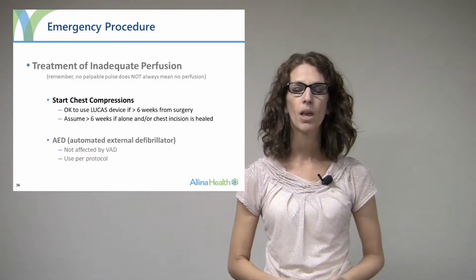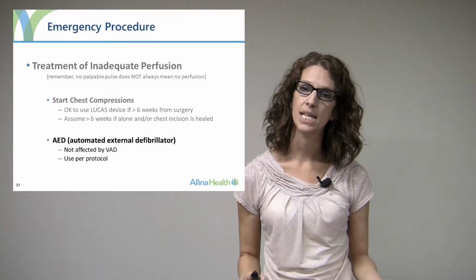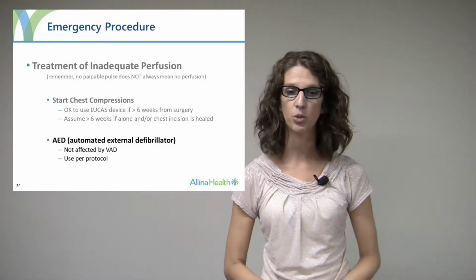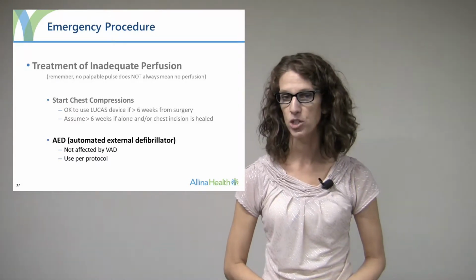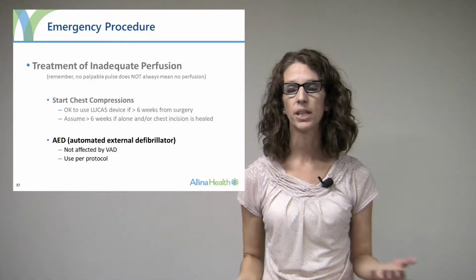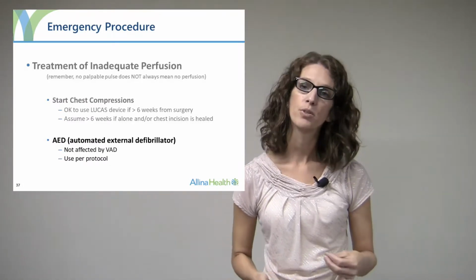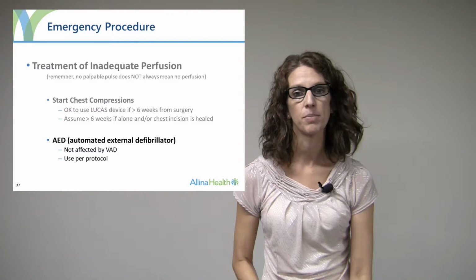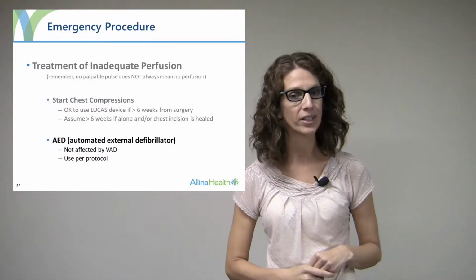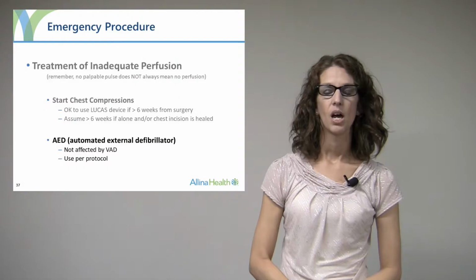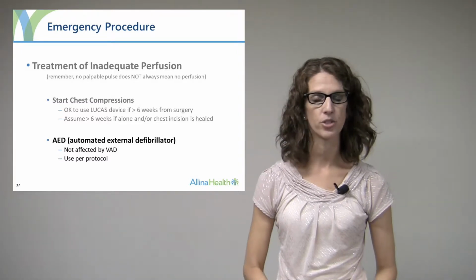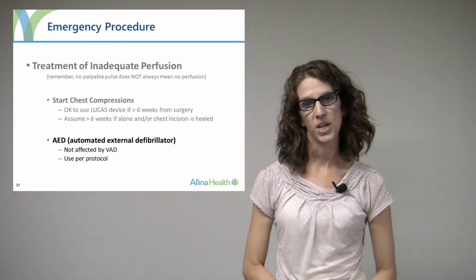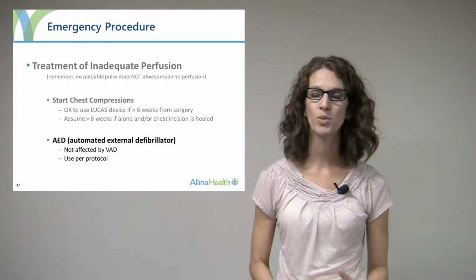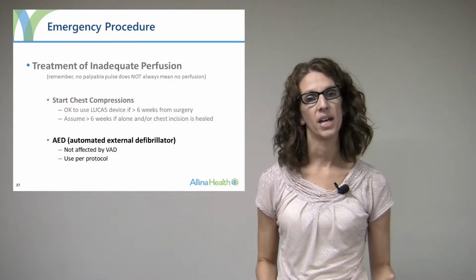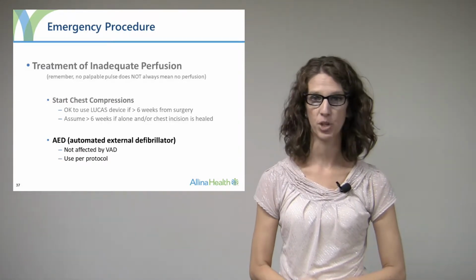With the electricity, you can use an AED or an external defibrillator, the same that you would with anybody else. The vast majority of our patients do have internal defibrillators, and we're going to let those cycle the way that they normally would. If you're using an external, we want to make sure that we're placing patches anterior or posterior. That seems to work better than placing over the left chest where the pump is at. Avoid that if at all possible. Another consideration with an AED or an external defibrillator is that it does not matter if the patient is on batteries or plugged into wall power. It won't damage the system, so go ahead and deliver that energy the same that you would with anybody else.